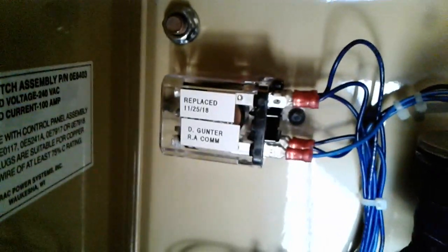Everything should be back to normal now. Just got through replacing this transfer relay. See what happens when we kill the AC mains. Lights out. Generator should start up in a few seconds. It has a time delay.